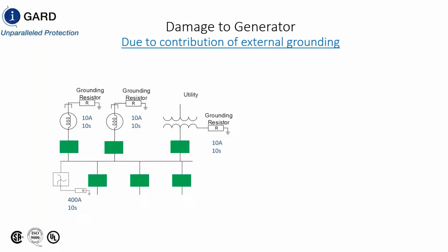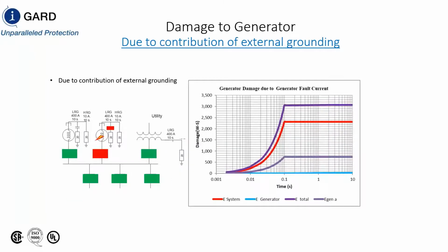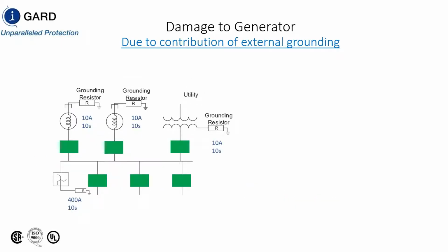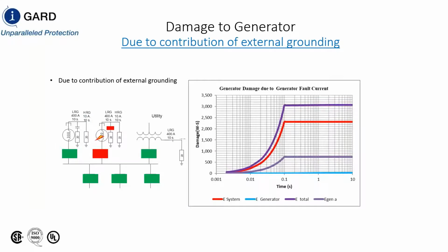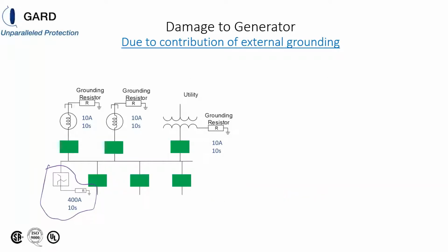If you wanted to avoid that complexity, because if you have this type of system and you want to add another generator over here, you have to add another hybrid high resistance ground in the system. So a simpler or alternative method of doing this is to use a Zig Zag transformer on the bus. The advantage of this system is that your fault current, irrespective of how many generators are connected to the system, is going to be 400 amps. So you could see that in this particular design, the multiple generators caused a multiple of 400 amps of ground fault current, whereas in this particular system, it doesn't matter how many generators are connected, your maximum fault current is always going to be 400 amps for 10 seconds.